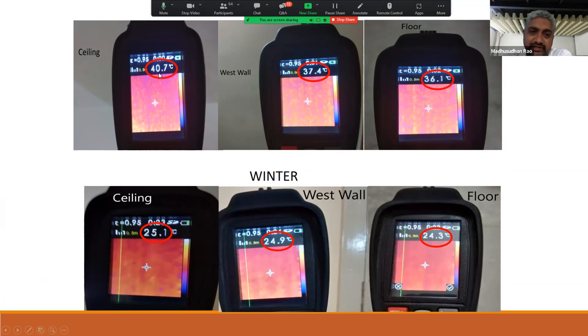This is in the night, by the way, around 9:30 or so. That is 40 degrees centigrade, 41 nearly. West wall is 37. Floor, which is not even exposed to the solar radiation or even outside temperature, is also 36. And the reason is that your building is one continuous thermal mass, right? The wall gets heated, it will conduct heat to the floor, right?